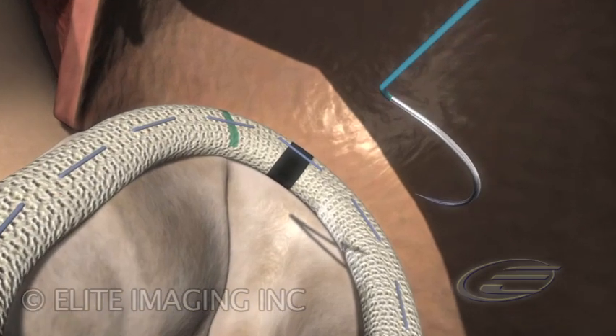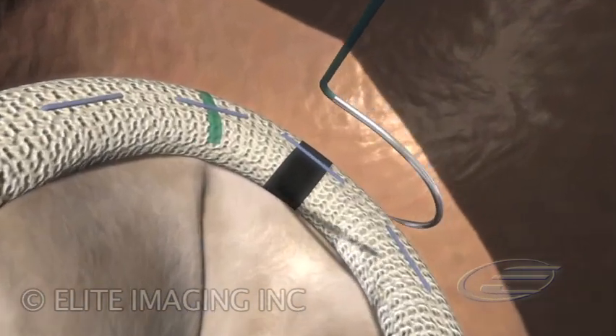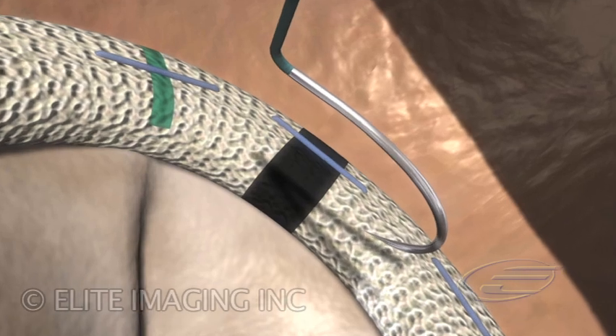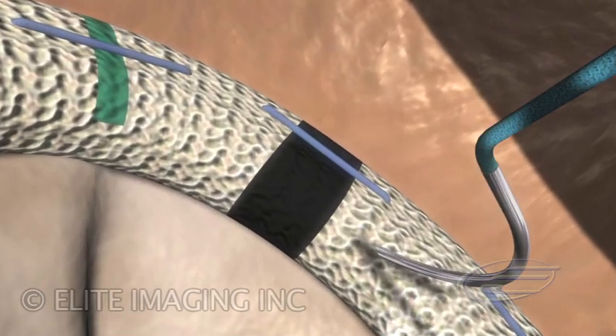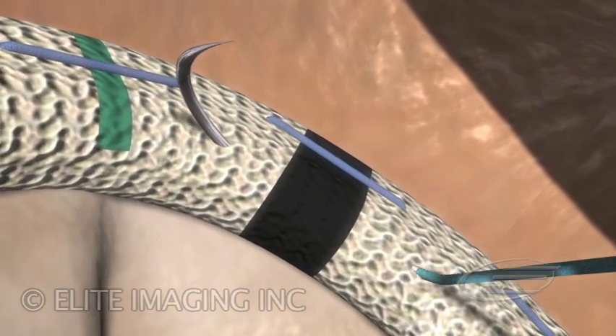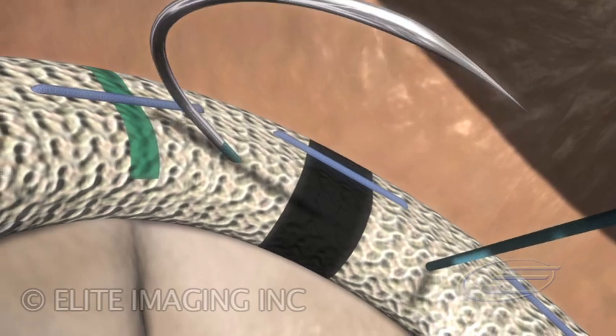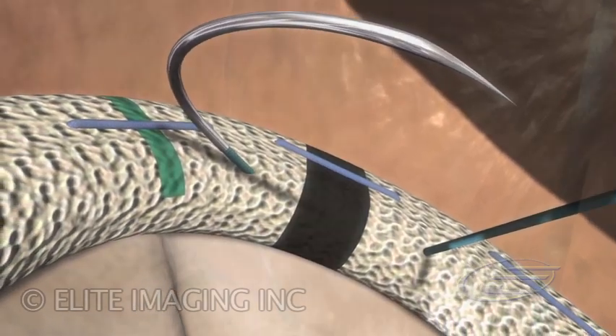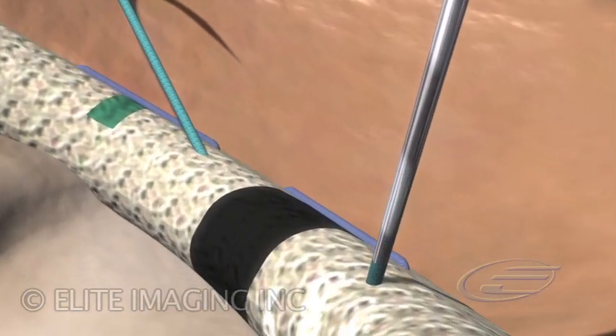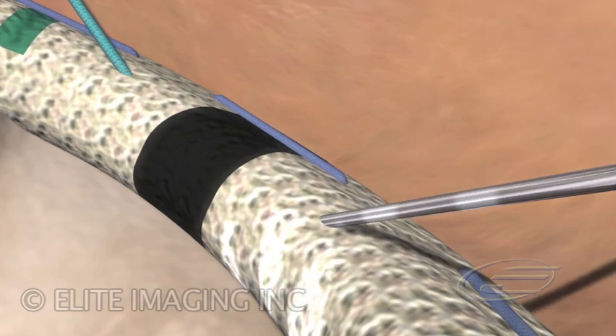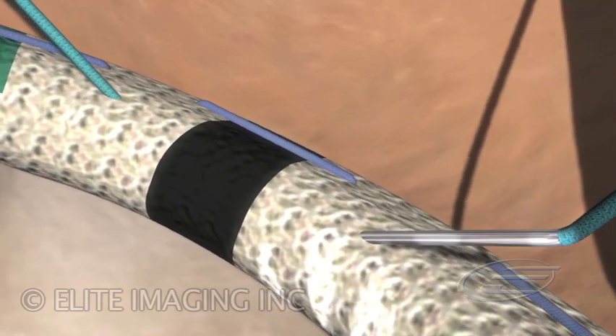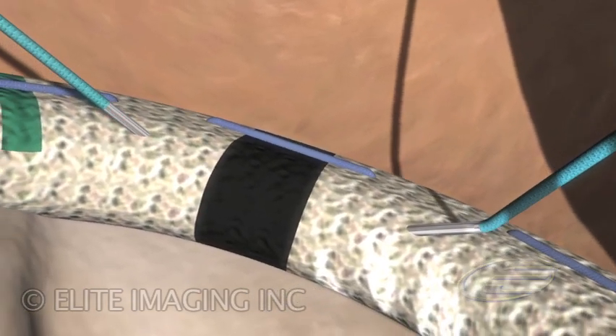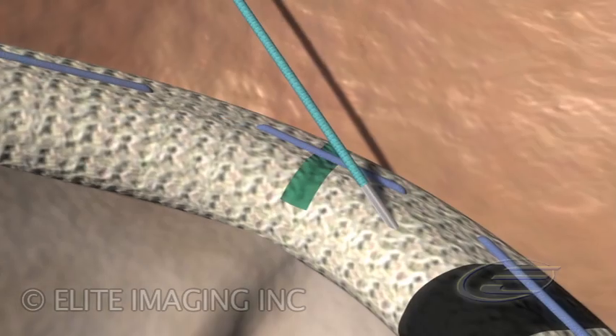The intraoperative activation requires an electrode to be placed in contact with the annuloplasty ring. A curved needle is introduced at the proper location, which is identified with a black band in the fabric cover. The suture is pulled until the electrode is centered underneath the covering. The electrode is now in contact for proper energy transfer and adequate anchoring.